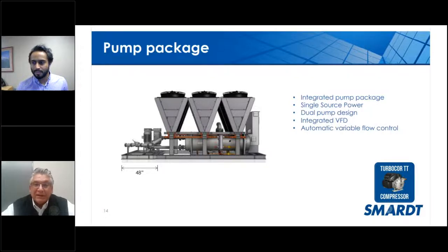Thanks, Jeff. As far as mounting those, do you typically see acoustic consultants requiring anything special for them? Or are those typically on springs? Yeah, as far as the machine, the chiller itself? Yeah. What is a benefit to Smardt is that it does have lower sound levels because of the design of the oil-free bearing. If you look at a screw machine, we've all heard those things whine at part load, right? And sometimes the vibration is an issue. With Smardt, because of the design of the compressor and using EC balanced condenser fans, the need for additional vibration isolation isn't required because the compressor sits on rubber mounts as well. So I hope that helps. All right, thank you. You bet.